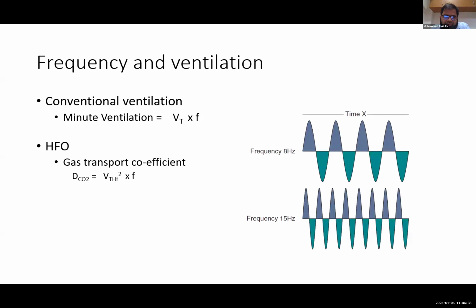If you increase the frequency, as in these graphs you're seeing on the screen, a frequency of 8 versus a frequency of 15: if you're using a frequency of 15, the TI time will decrease compared to a frequency of 8. Because your TI time is less, your tidal volume decreases significantly. Even though you are increasing the frequency, your tidal volume is decreased significantly, and the gas transport coefficient of CO2 is almost proportional to the square of tidal volume. So even though you increase the frequency, because of the decrease in tidal volume delivery, babies will have CO2 retention. That's why it is inversely related compared to conventional ventilation. If you increase frequency, the delivered tidal volume will decrease, so babies will have CO2 retention.